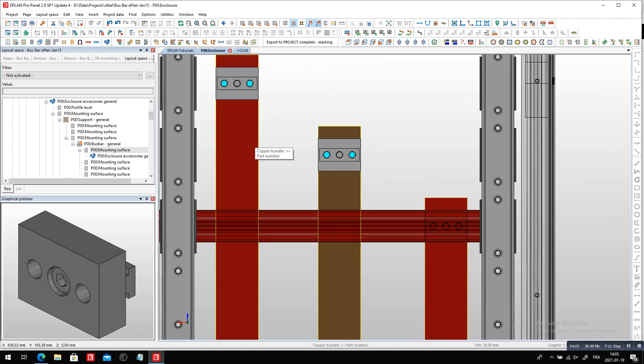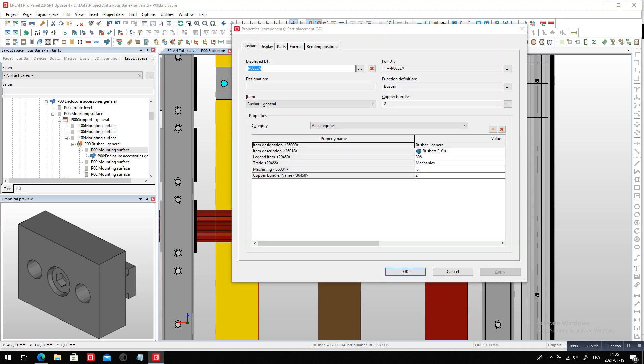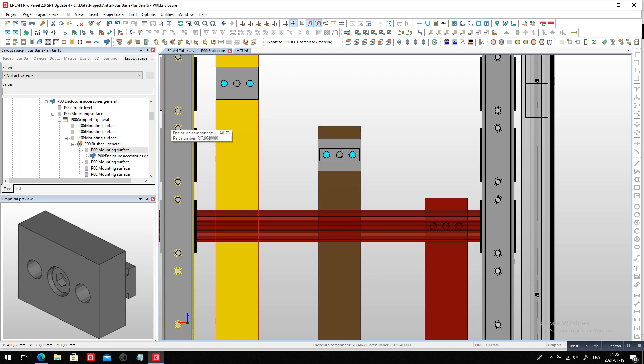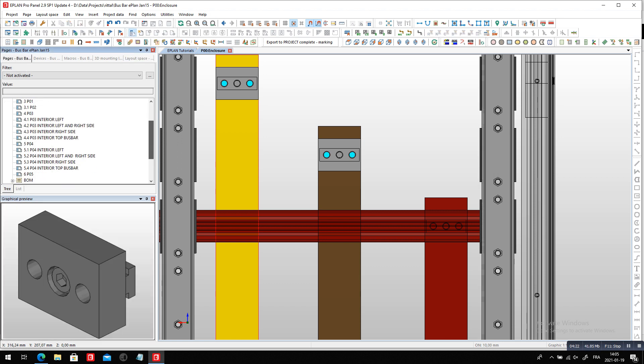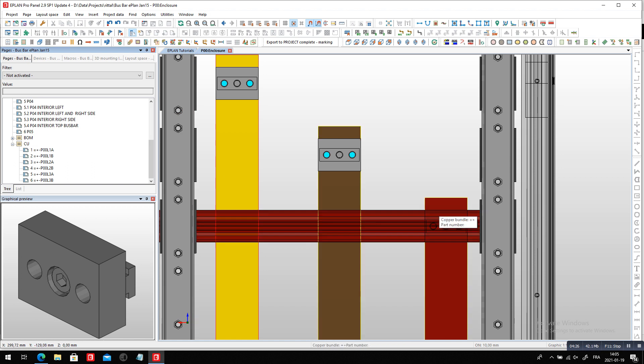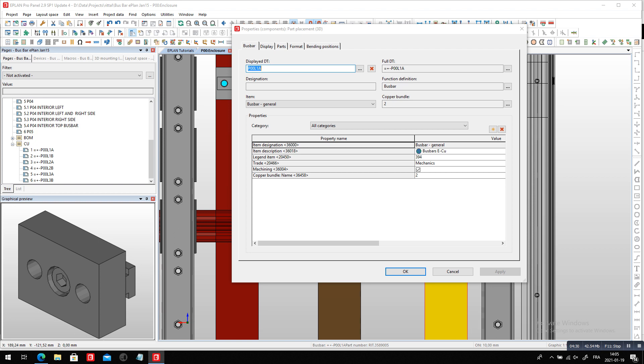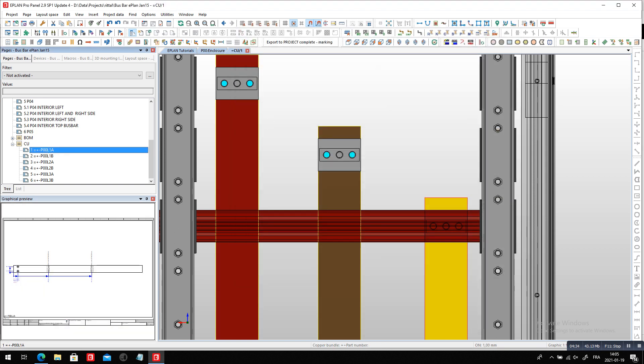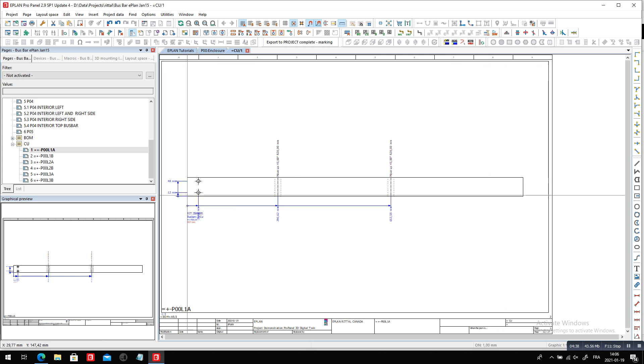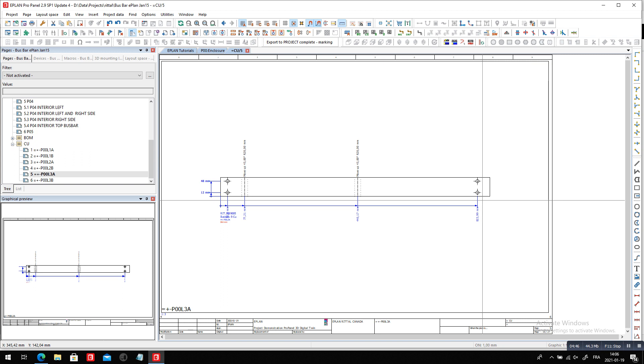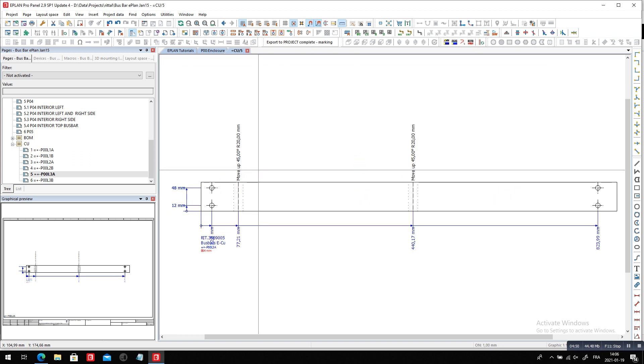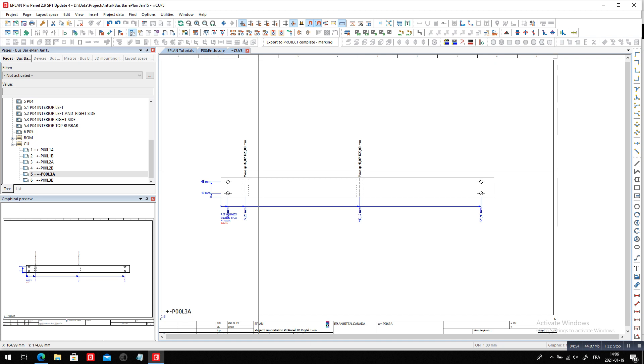Now these bus bars are named P00-something, L1, L2, L3, and they automatically generate so-called copper unfold reports. I'll update them — there's still one that hasn't been done yet so we can compare. For L1A, it only has holes on one side, not the other. For L2, we have holes on both sides, automatically generated. You can see exactly the two 45-degree bends that were in that particular copper bar — very precise.